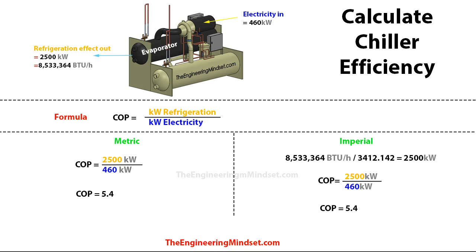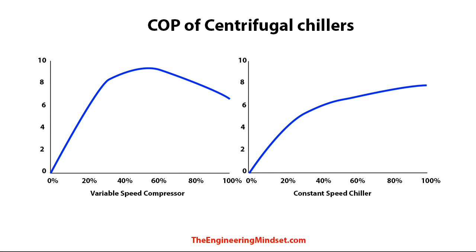A COP of 5.4 is very good. What this means is that for every one kilowatt of electricity that you put in, you will get 5.4 kilowatts of cooling out — so you get five times your money's worth of electricity out in cooling. The COP of a chiller will actually vary throughout the amount of load that's placed on it, so throughout the year and throughout the day as well, unless you've got a constant load.